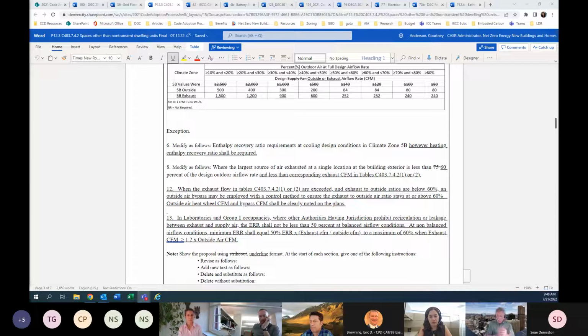I think, okay, so 12, actually, it's a good, there's design issues that this comes up in, and I could say all the time, but this is simply a 10,000 CFM outside air building that only needs 1,200 CFM of bathroom exhaust, right? Just an office building with a high occupancy. So that could happen. It does happen.